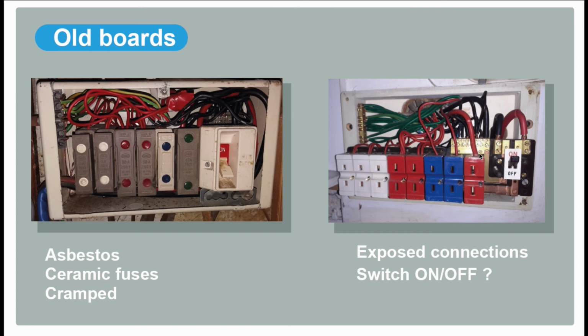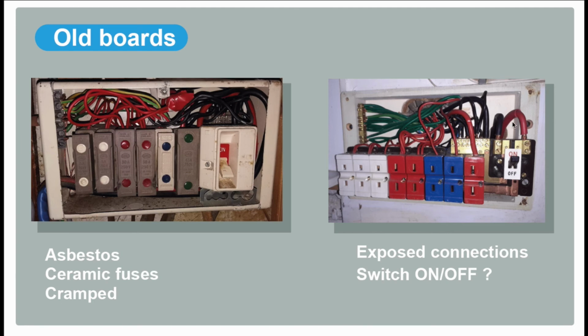And here's another example. This is a slightly more modern one, like the rewirable fuse box, the Wylex I'm using for these examples. But I'm not particularly happy with this one because the plate is missing here, the cover is missing, so you've got access to the live terminals. There's also often little shrouds over these connections, so it's not a comfortable board to work in because we can't isolate this. These tails here are going straight into the supply cutout. There's no isolation, so even though we can switch the rest of the board off and work safely on the circuits, we can't switch this bit off here, and it's not a nice environment to be working around a big lump of live copper like that. So no, you've got to take a view if it's safe to use the old board for your temporary supply.